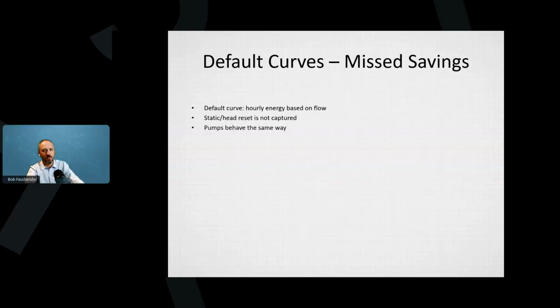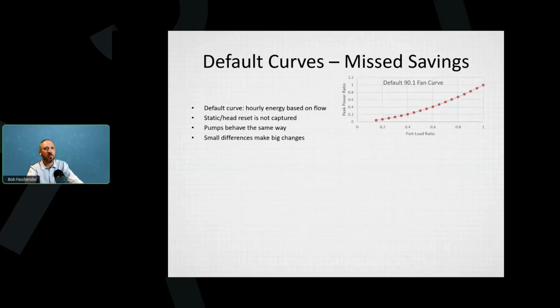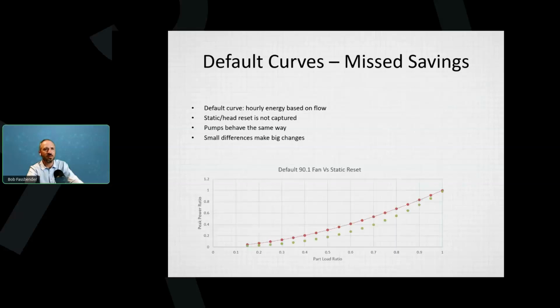Okay, so when you use the default curves, you can miss the savings. Again, as a performance contractor, if the actual building outperforms your model, that's all good. But it doesn't capture the static, or the head, as we discussed. So small differences in the curve make a big change. This is the same for pumps or fans. This is a slight adjustment to that 90.1 fan curve, if you're modeling static reset or running static reset controls. This fan, the one in green, used almost half as much energy as the one in red.